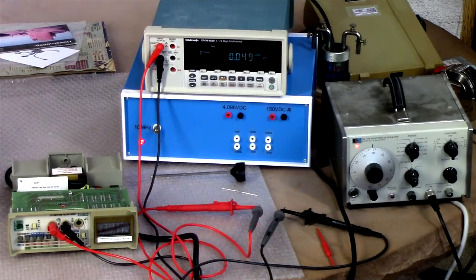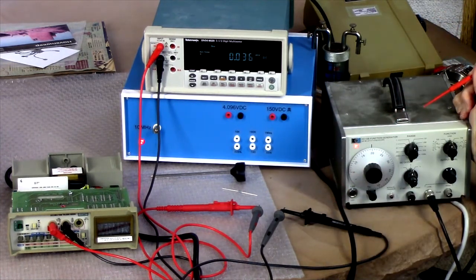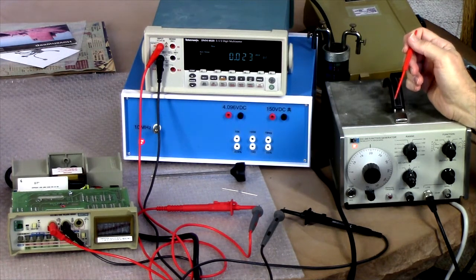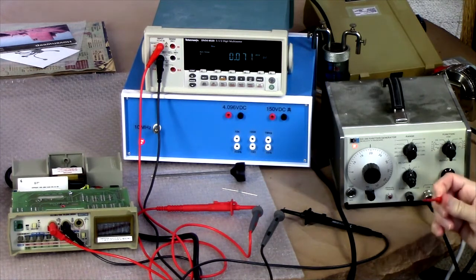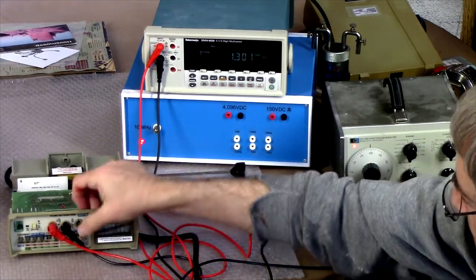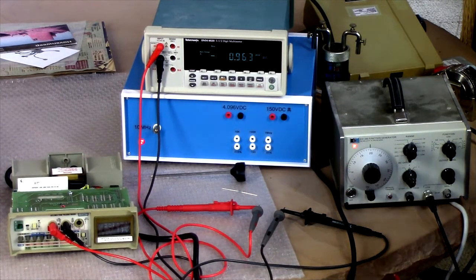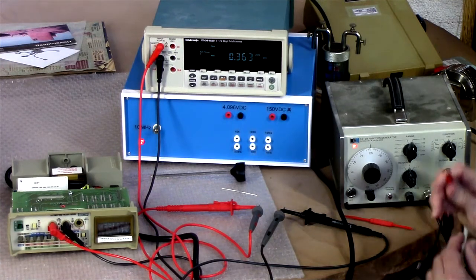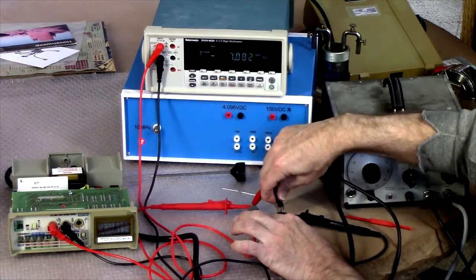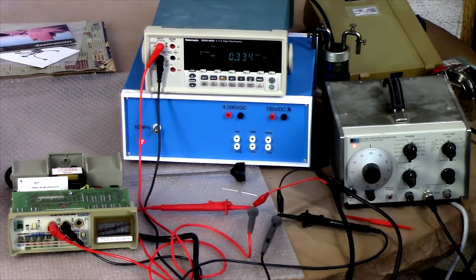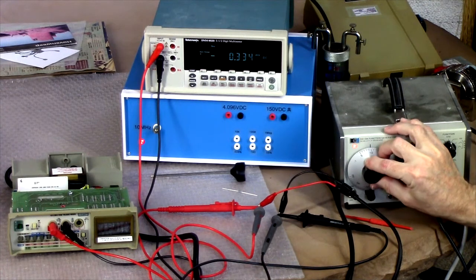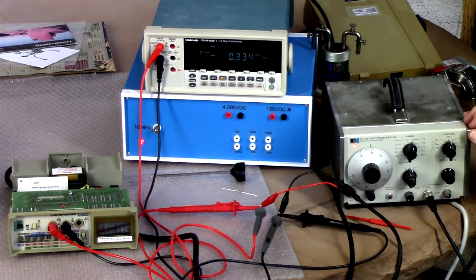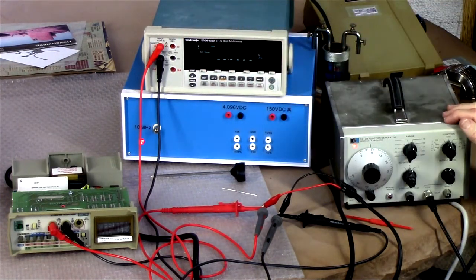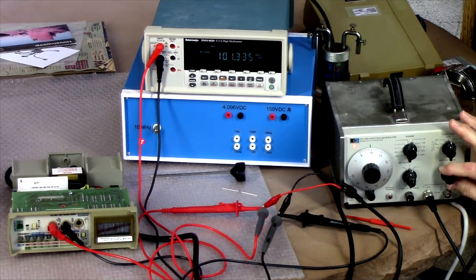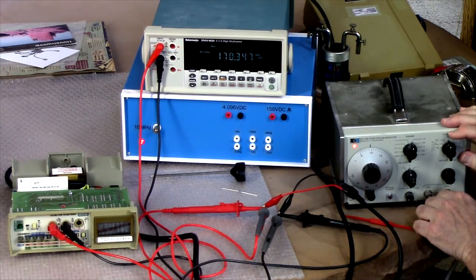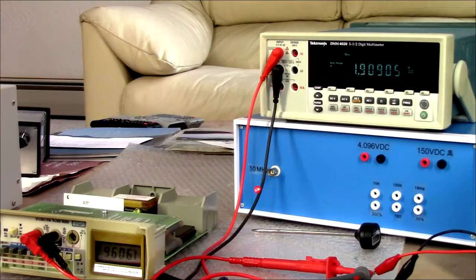Assume that's correct. All right, and for AC, you can see I've moved the camera a little bit. I'm going to use this generator and just do the best we can with this. So we're setting it to AC volts. We're starting on the 2 volt range. I don't know what this is currently set at. And it wants 1.9 volts RMS at 100 hertz. So I'm going to turn that down to approximately 100 hertz. I'm going to times 10 scale there. AC volts. It's 101 millivolts. Probably want more than that. I want 1.9. Okay, that's good.